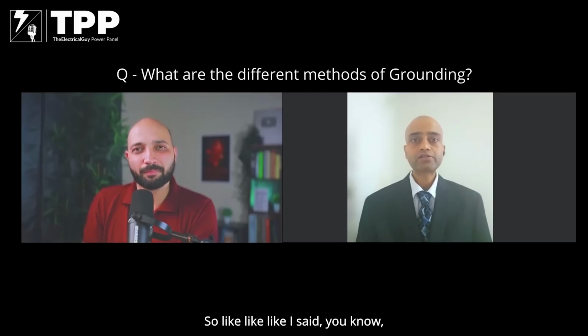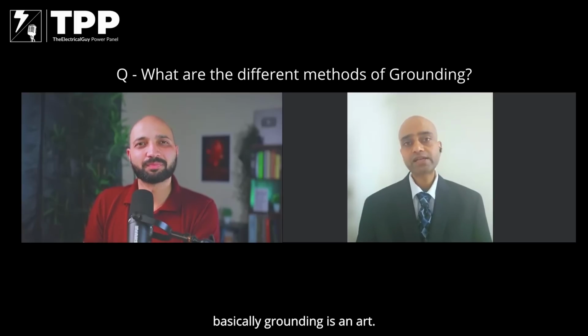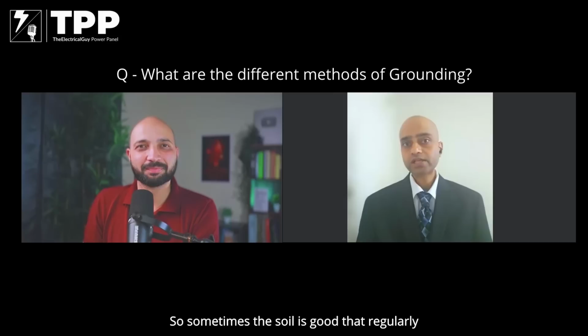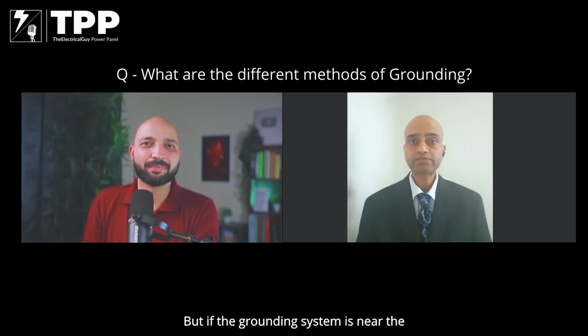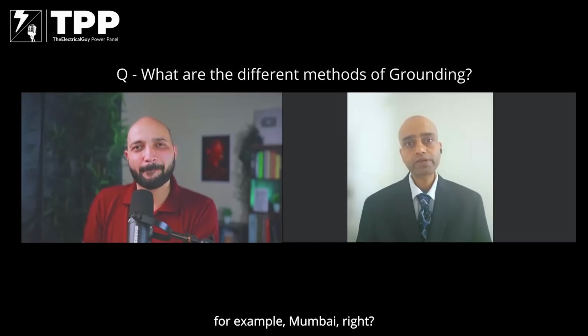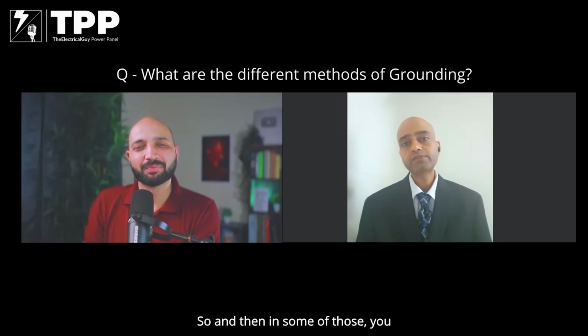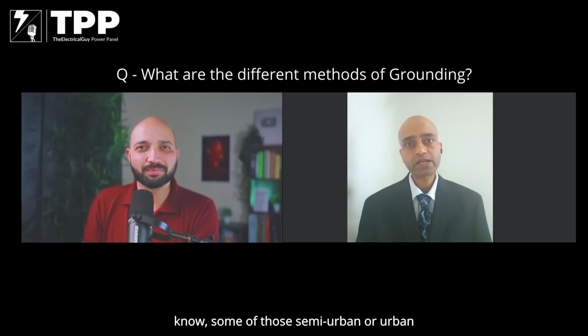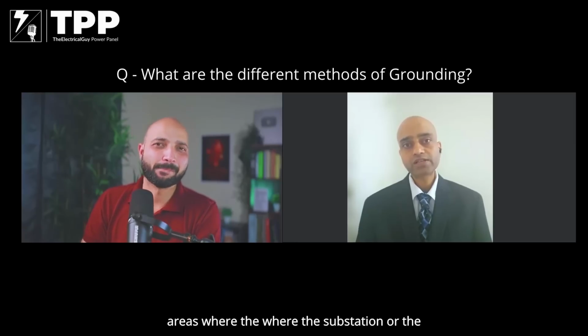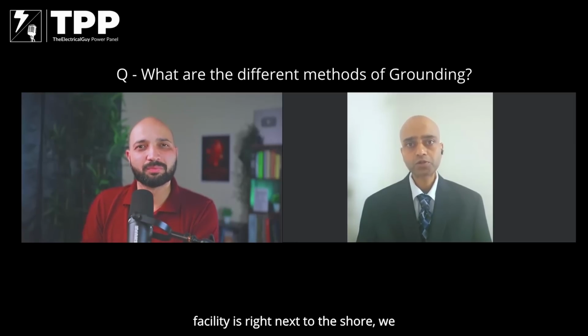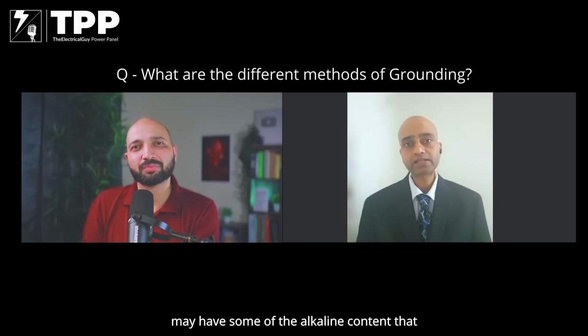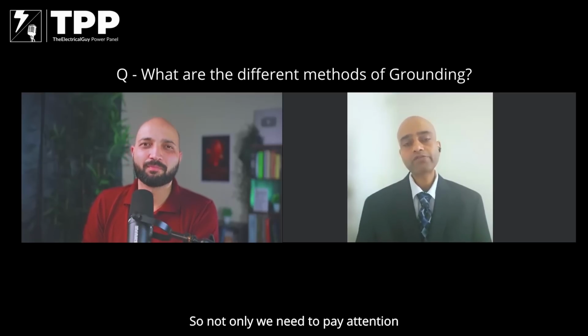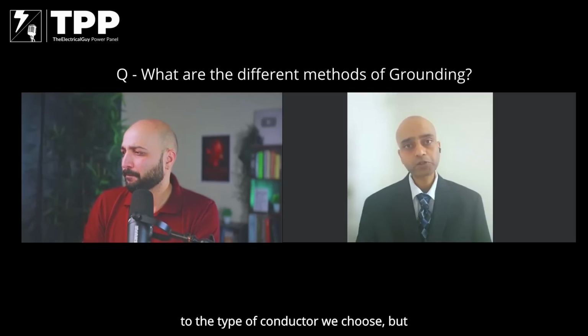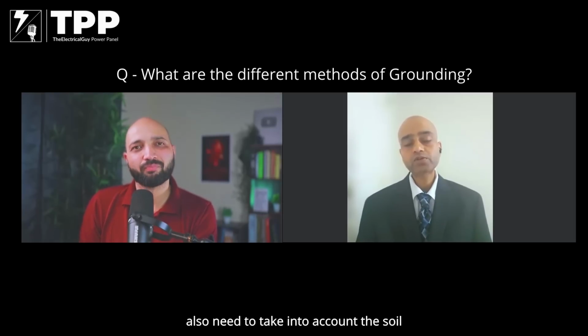Like I said, grounding is basically an art. Sometimes the soil is good, like regular clay, and we may not have corrosion. But if the grounding system is near a tropical area, like for example Mumbai, in some semi-urban or urban areas where the substation or facility is right next to the shore, we may have alkaline content that may or may not corrode it. So we need to pay attention not only to the type of conductor we choose, but also take into account the soil corrosivity.